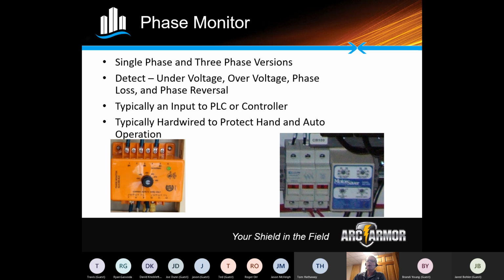So a little higher scale, with a few more components attached to a power monitor than a phase monitor. Your typical phase monitor is going to be in that $500 range or less. Sometimes people will say, you have a $500 piece of equipment protecting a lot of more expensive equipment. Sometimes these are not as reliable as they need to be, but they will work in the correct situations to protect the equipment. Questions on phase monitors?